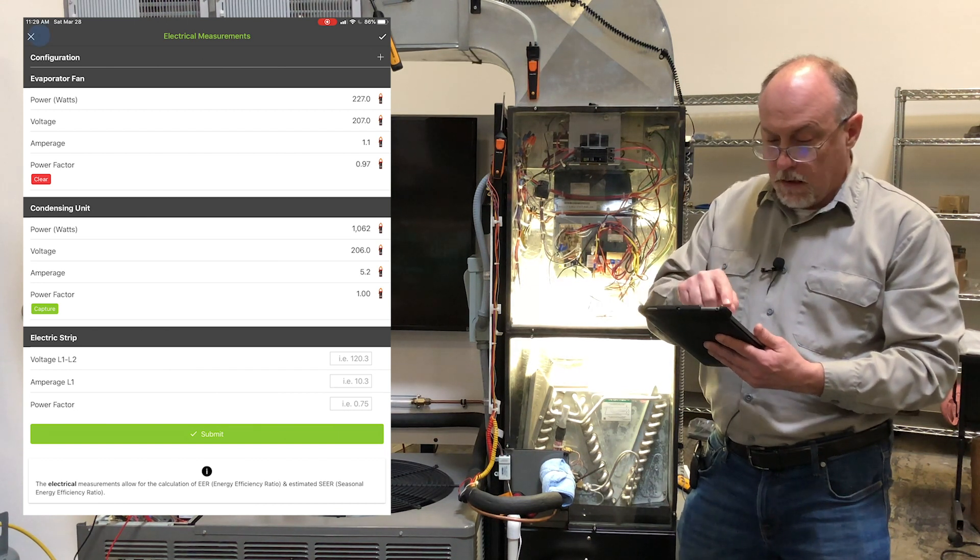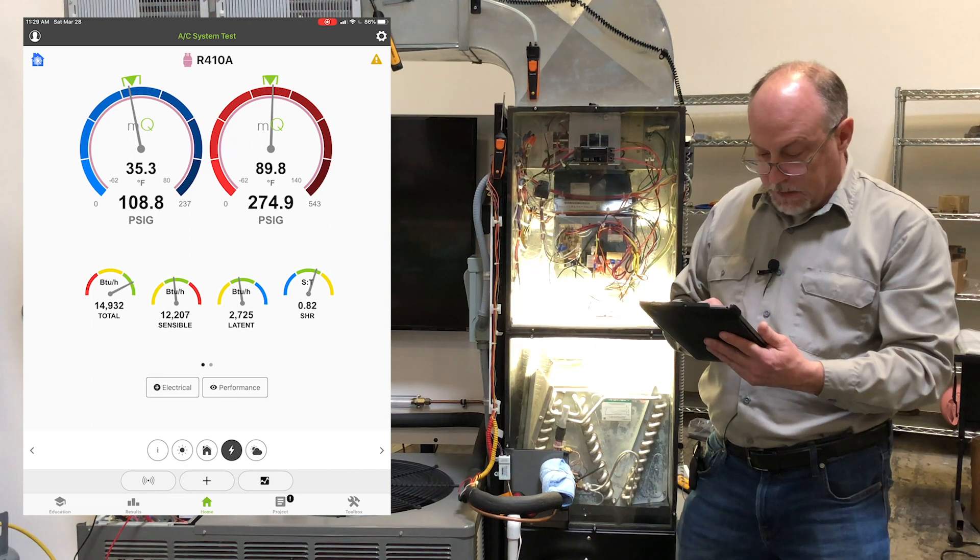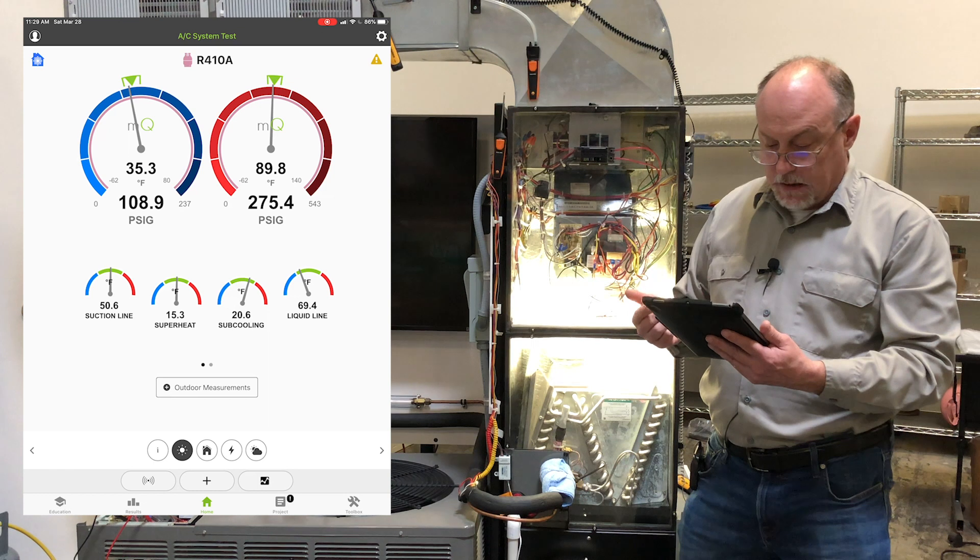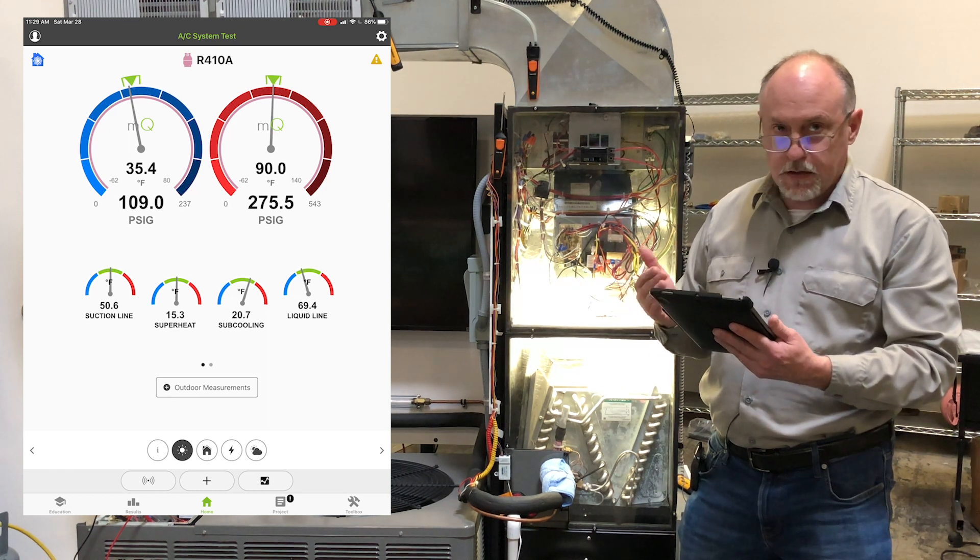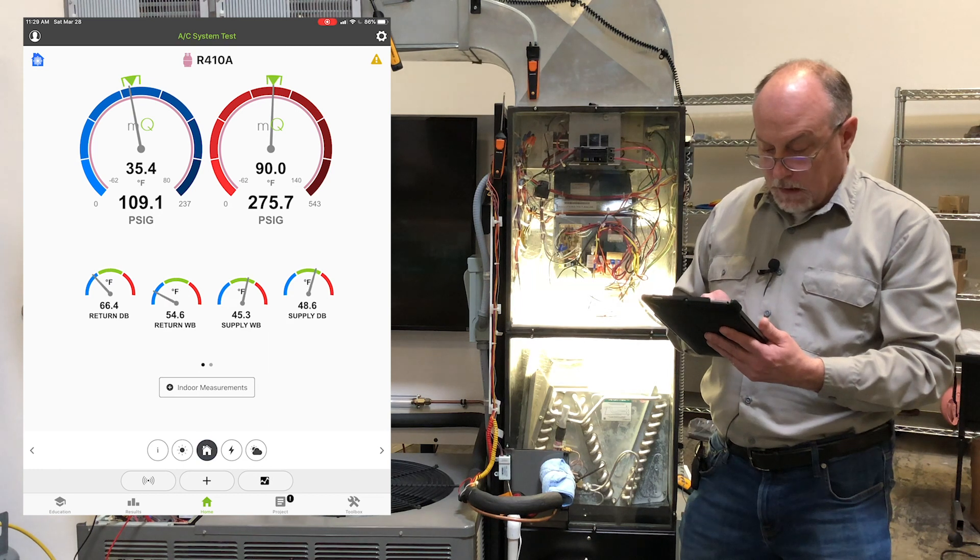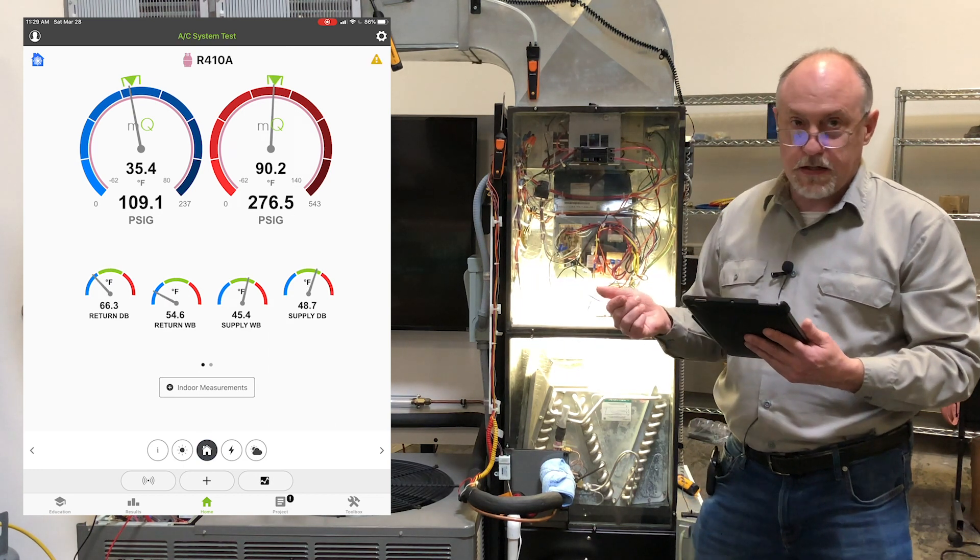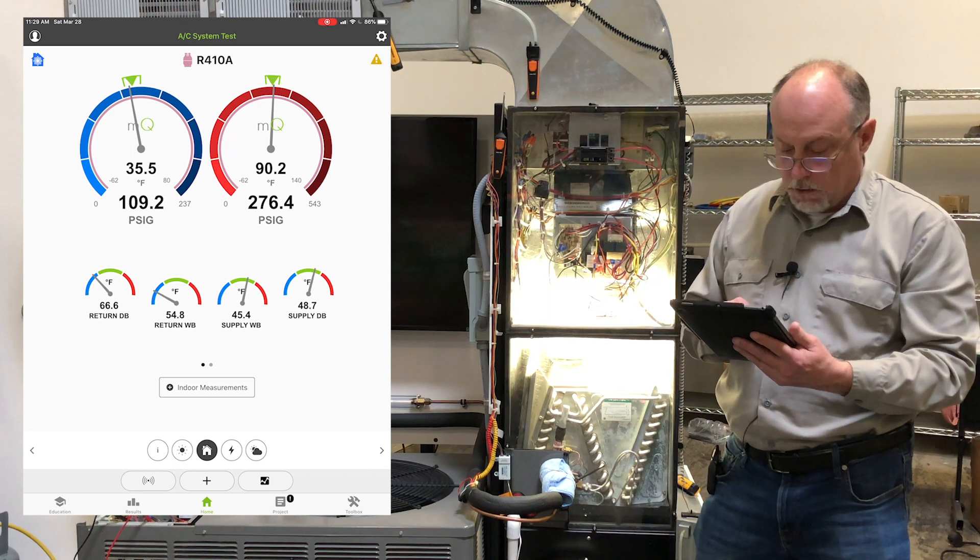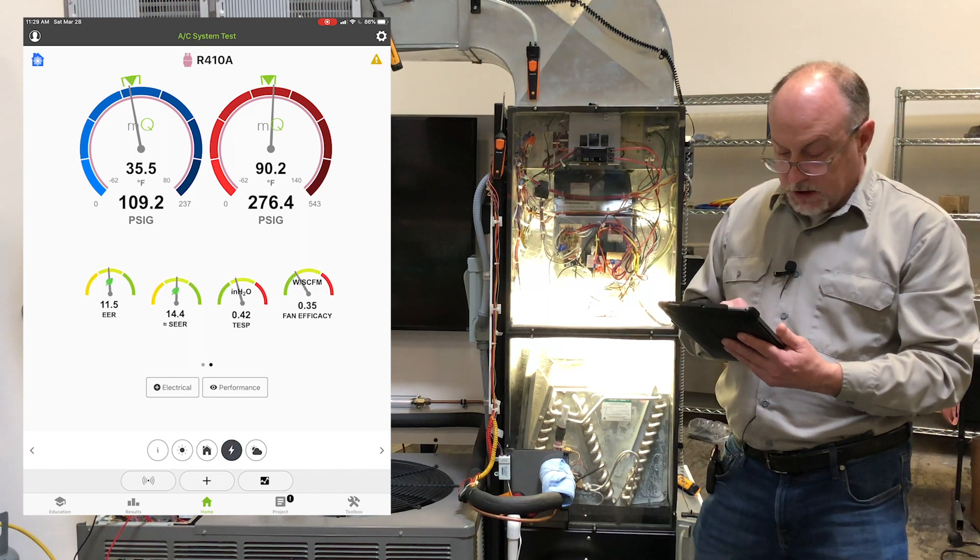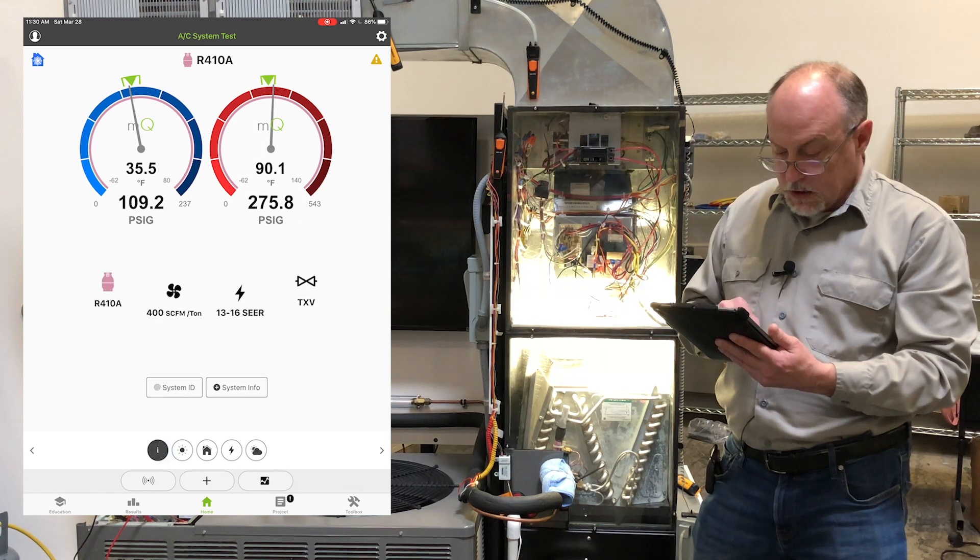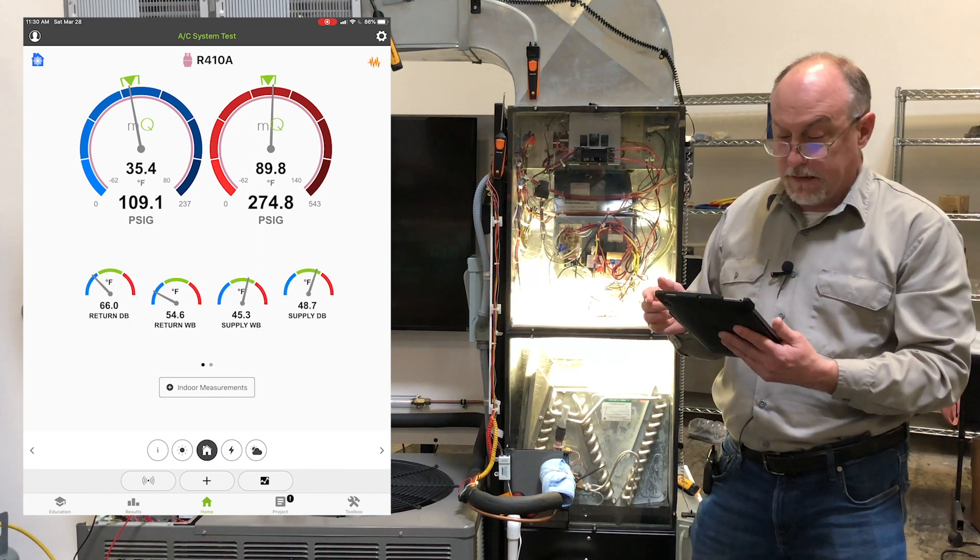So now I've got everything up and running here. And let's talk a little bit about what these targets look like. So you can see I've got my suction line superheat, my subcooling. Everything is in the target zones. Return air is a little bit low. It's 66 degrees in here. Supply air wet bulb and dry bulb are in the target ranges. Electrical all looks good. EER looks good on the machine. So everything looks like it's running the way that we expect it.